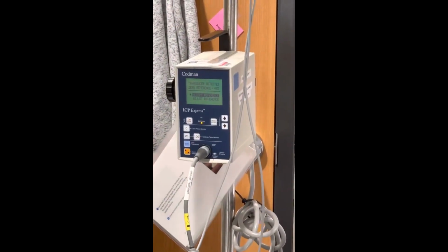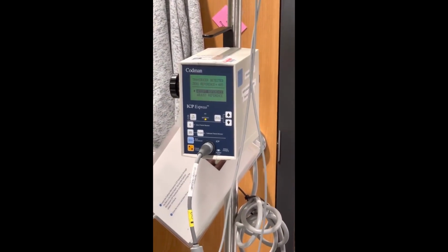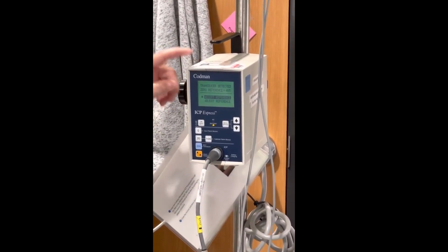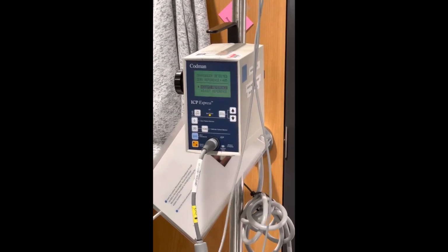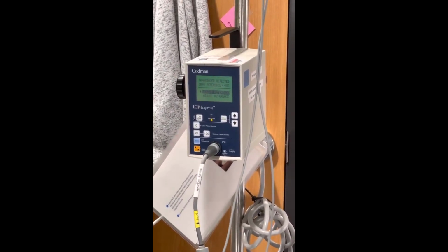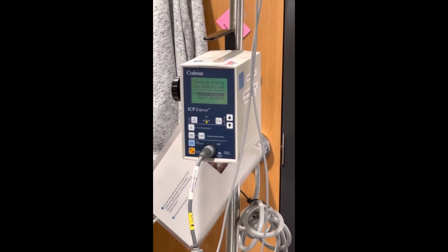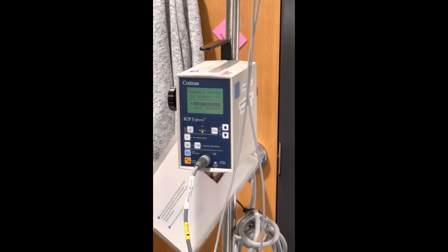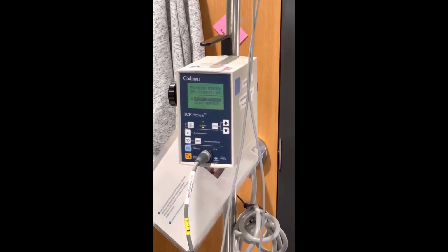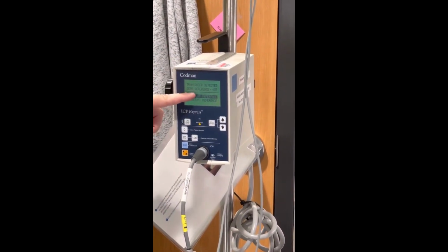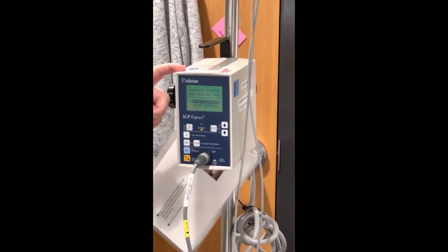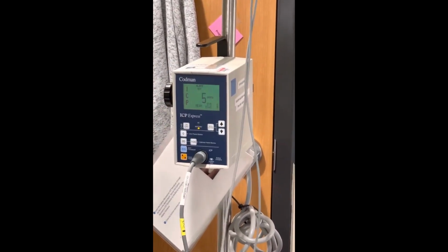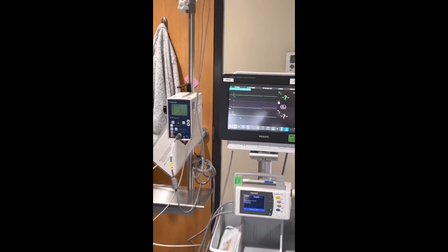And here is where it's telling us the transducer detected that the zero reference is 485. This is where you're going to reference up here at the top and see what was written down. Or if for some reason it's not there, look in your OR notes. This is that number that is specific to this transducer. If this number is off by 1 or 2 or whatever it may be, you can adjust it. You can go down here to adjust reference, and you can adjust it up by 1 or 2 to whatever you need it to be at. But you need to make sure that this number matches. It says ours is 485, and mine says it's supposed to be 485, so I'm going to accept that and press menu enter. All right, and now we are seeing our ICP, and it's matching.